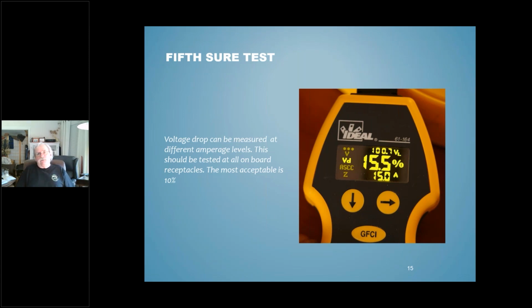Now, of course, the problem with that, if you're measuring on the dock, is that it's giving you a total reading, and to isolate where the fault is is a little bit challenging because you really have to work your way down the dock towards the source of power to isolate where the problem is. But I'm not aware of any other tool other than, well, there are other tools like the Ideal SureTest, but with this, you can actually determine if you've got too much voltage drop. Again, for voltage, the maximum ABYC allows is 10% plus or minus. Frequency, 5% plus or minus.